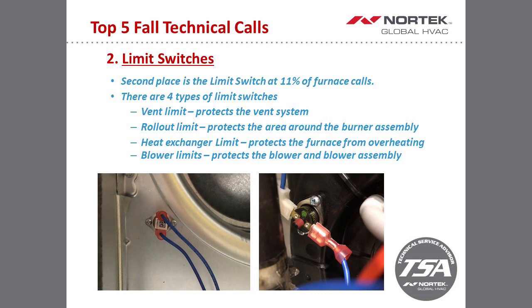The heat exchanger limit is essentially your main air limit. If that is going off on you, the first question we ask is, what is your temperature rise? So if you're roughly around 50 degrees on your temperature rise, you're fine. If you're pushing 60 degrees or more, we may have an airflow problem. Also, what we'll ask is, what is your return air temperature? Because a lot of times guys will give us an adequate temperature rise number, say like 45 to 50 degrees, but the return air vents will be either high in the ceiling or on the upper portion of the wall, which obviously, hot air rises, and that'll give you a higher return temp, which could be a potential issue if your main air limit is tripping.